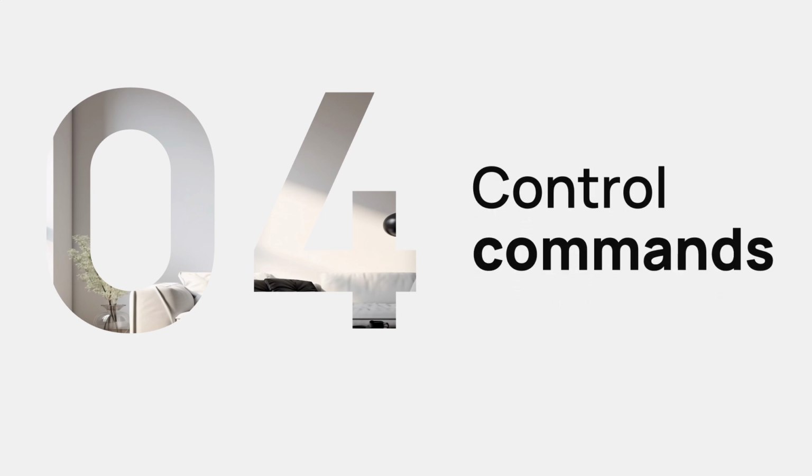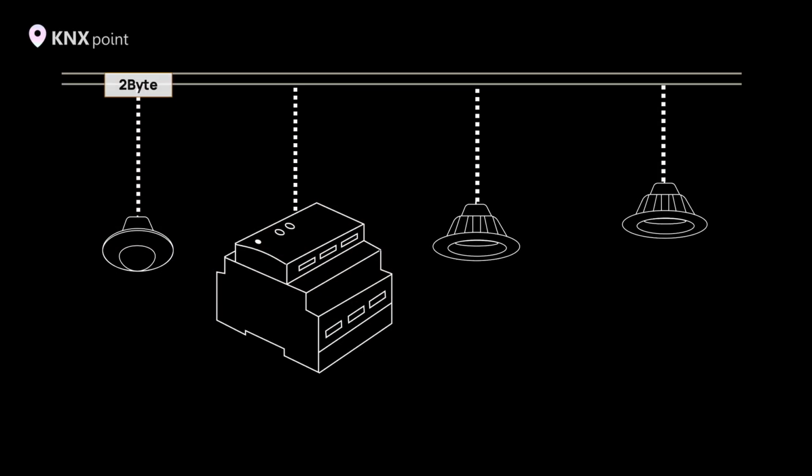DALI commands. In the DALI bus, commands from control devices are sent directly to actuators. The system is decentralized and does not require a central master controller. A typical command is 2 bytes long. There are also response messages 1 byte long and commands for color control 3 bytes long.